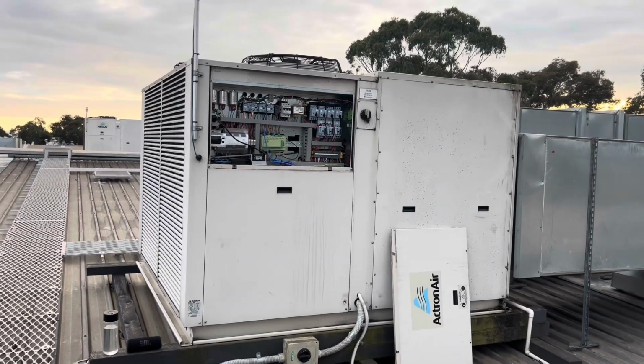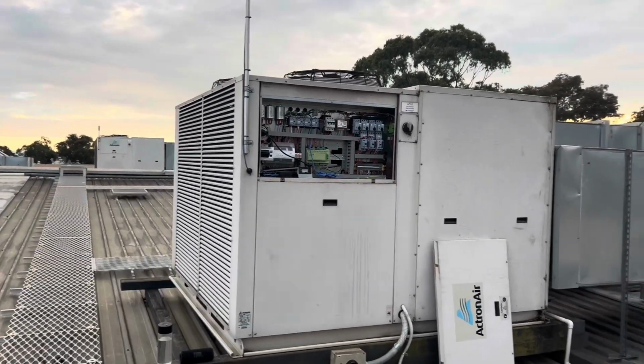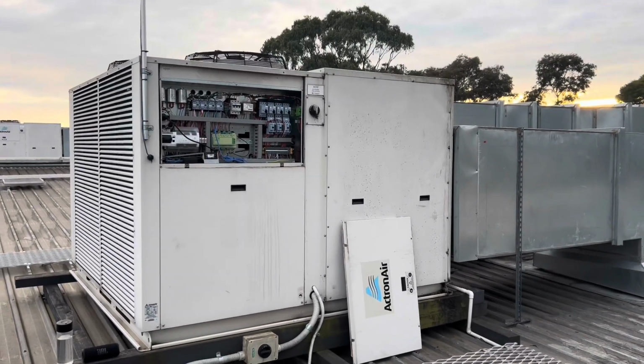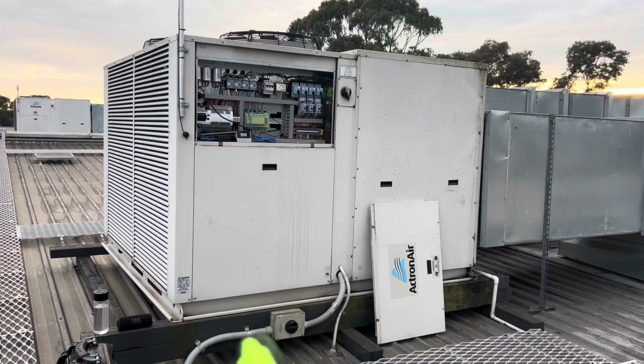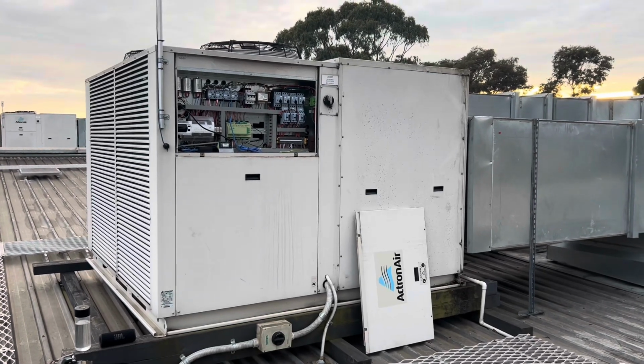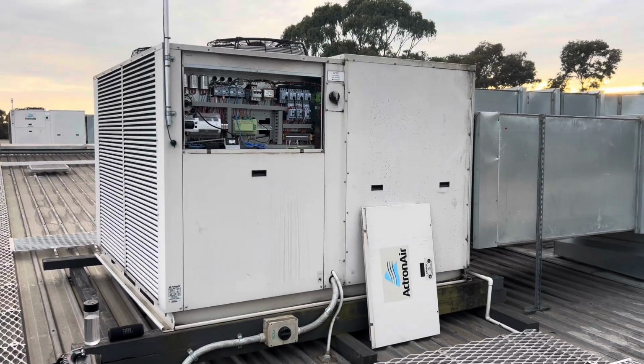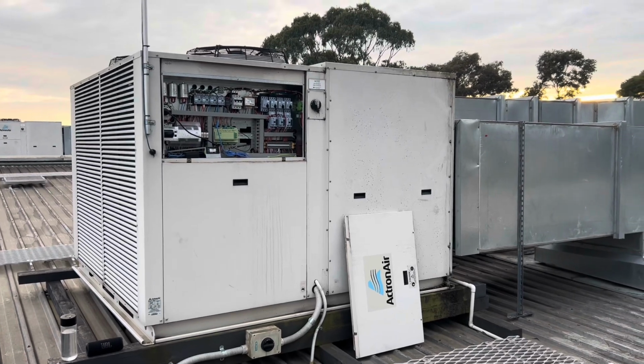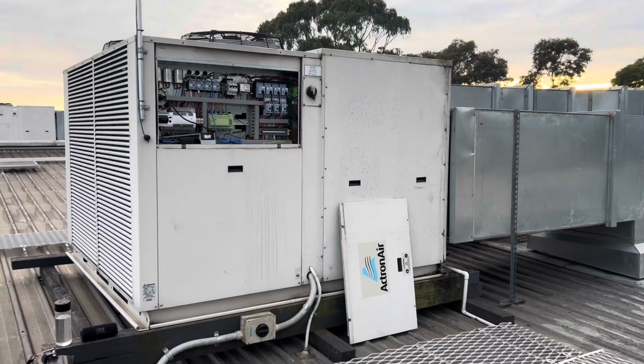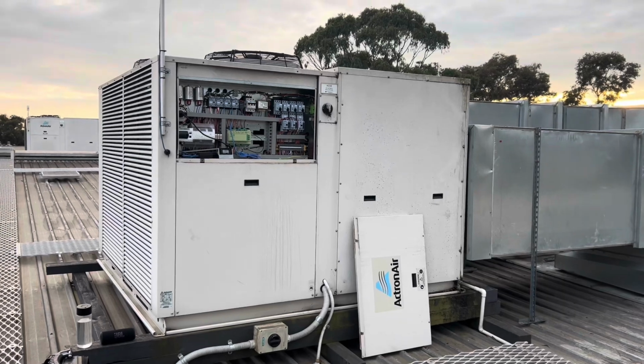Today I'm here to have a look at this Actron Air package unit and that one over there. Basically what happened is, on a maintenance, this one had faulted out on high pressure. It was still running, it had just logged a fault. So I probed up and found that I had a really high TD across the coil. I investigated further, filters were all clean and the coil was clean.